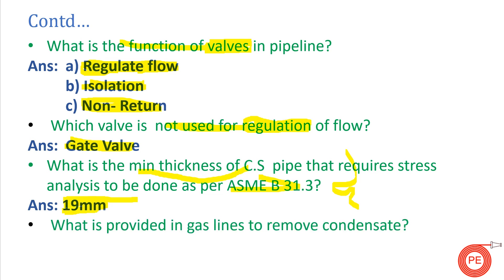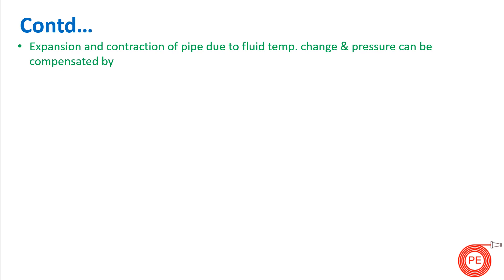The next question is: what is provided in gas lines to remove condensate? Gas contains moisture content which forms condensate, and this must be removed from the lines so it does not harm downstream equipment. Drip legs are provided to remove condensate from gas lines. Similarly, for steam lines, steam traps are used to remove condensate.